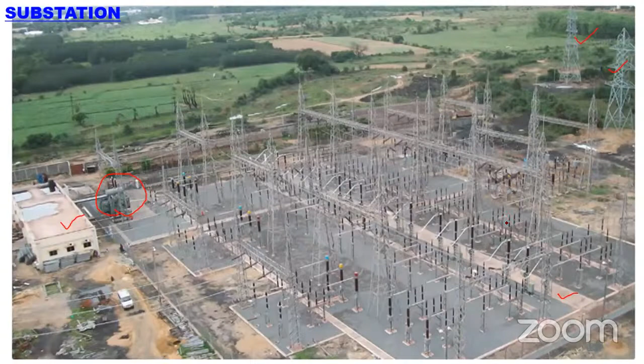Okay, let's take a little closer view of the transmission line and how it is connected to your line feeder. Okay, so from this transmission line, let me explain the components first, then let's understand the scheme. So this is the tower. From the tower, you can see a conductor coming, and the first component is the lightning arrestor. This is actually a line reactor. It just helps to compensate the line. Okay, this is another component. Then this is the current transformer. Then this component is a circuit breaker. Then this is called the gantry.